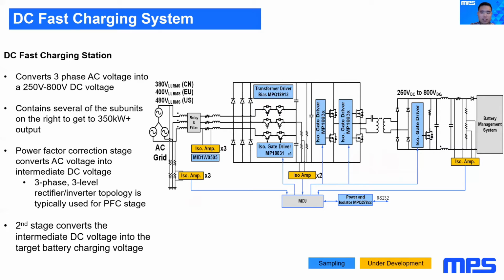The first stage is a power factor correction stage, which converts the AC voltage from the power grid into an intermediate DC voltage bus between 800 volts to 1300 volts. A three-phase, three-level rectifier/inverter topology is commonly used in this PFC stage, referring to a three-level converter that can interface with a three-phase power grid.